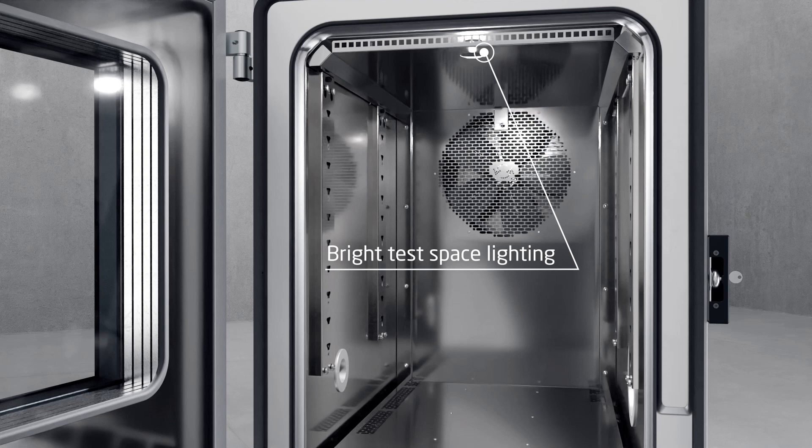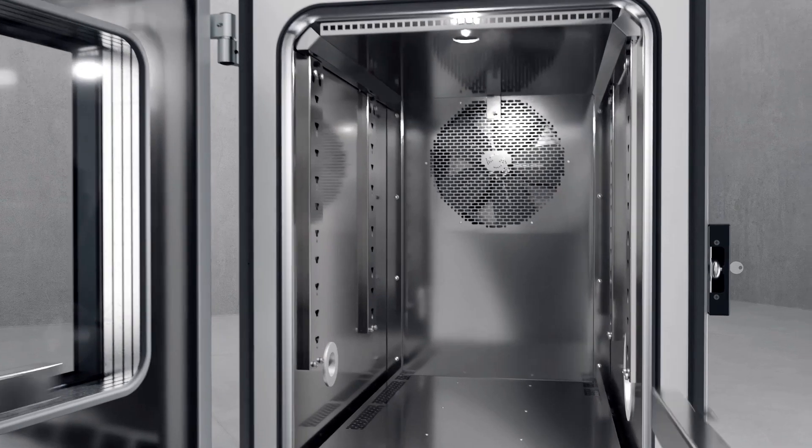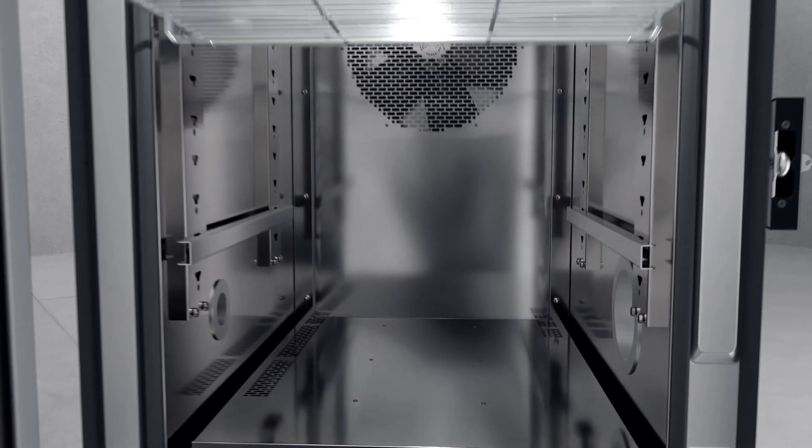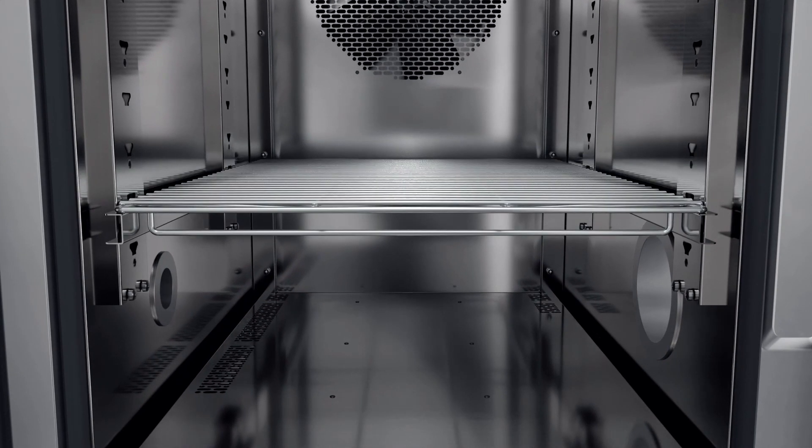The test chamber consists of a steam-tight welded stainless steel container which ensures easy cleaning. For better handling and more flexible preparation as well as execution of tests, the side walls are equipped with a rail system. This allows the combination of conventional insert shelves with pull-out rails. In addition, special screws are integrated into the side rails for easy mounting of test setups and special constructions.